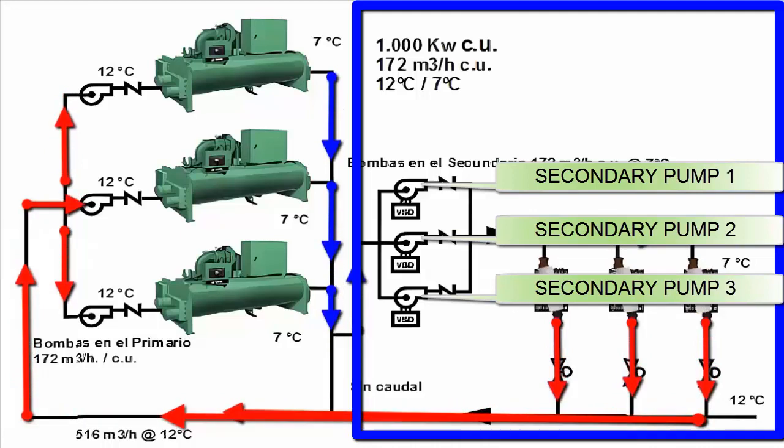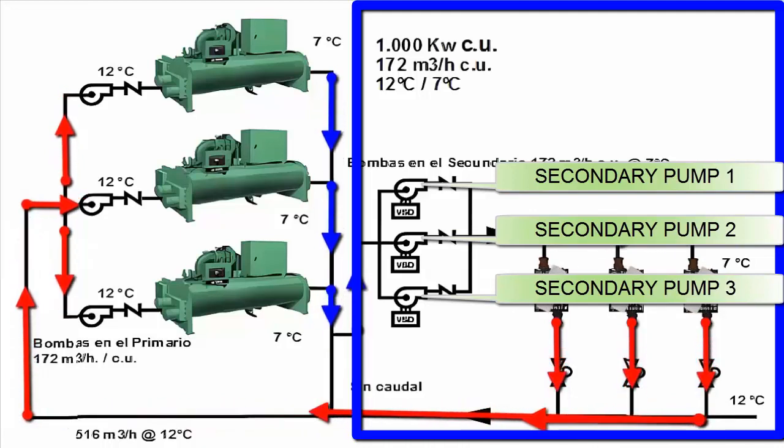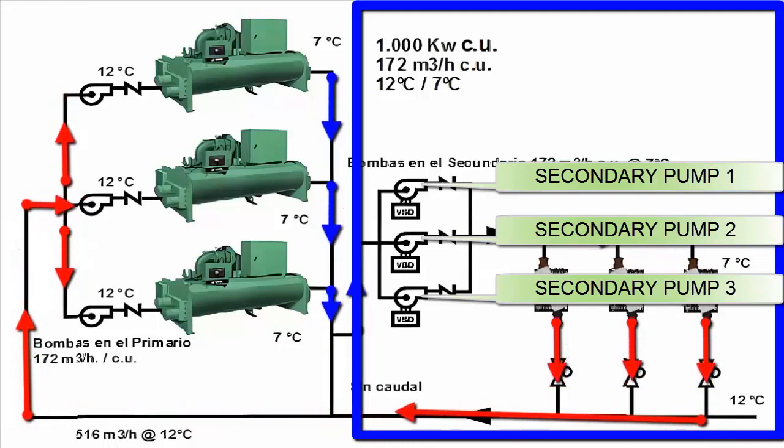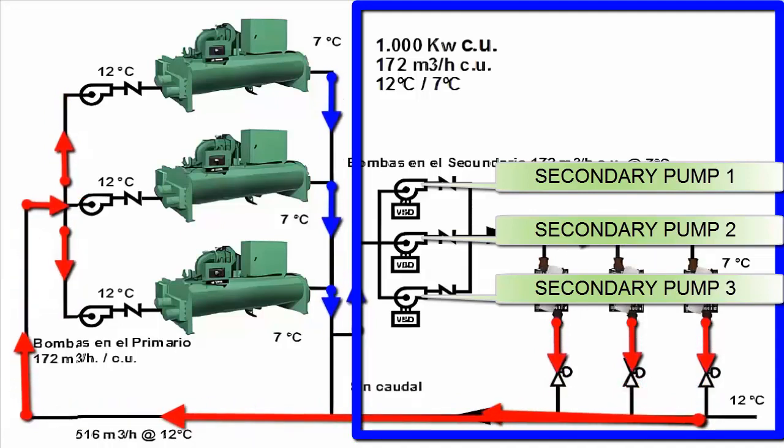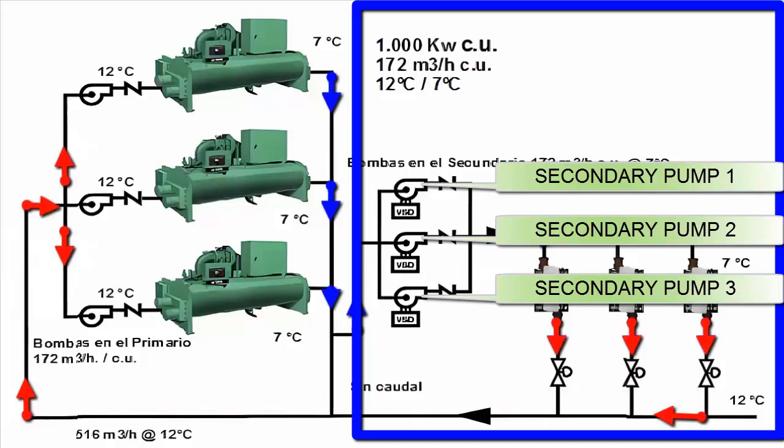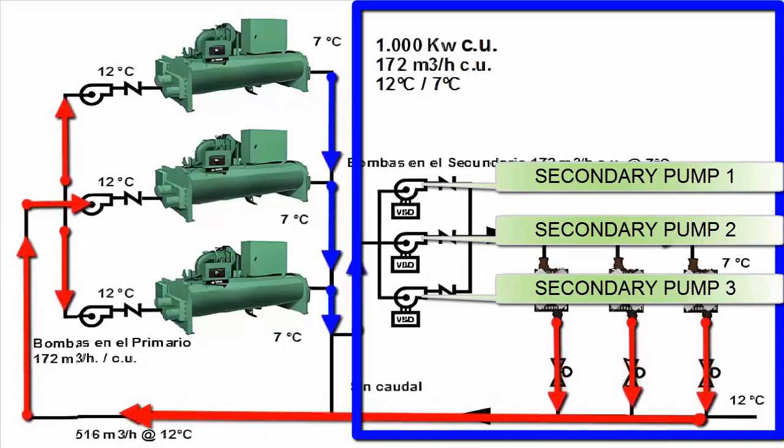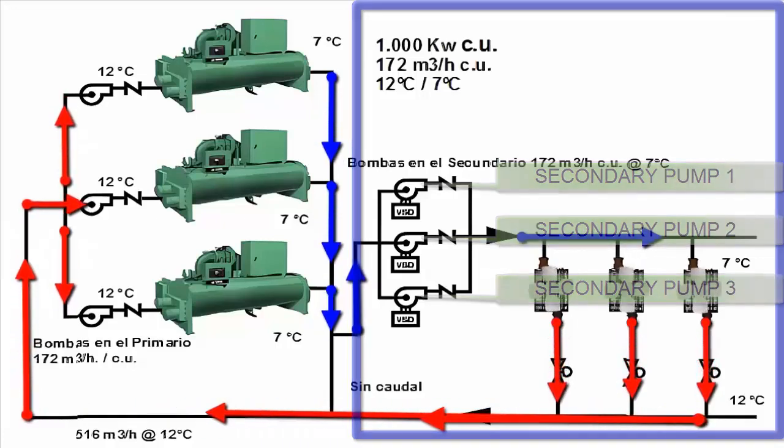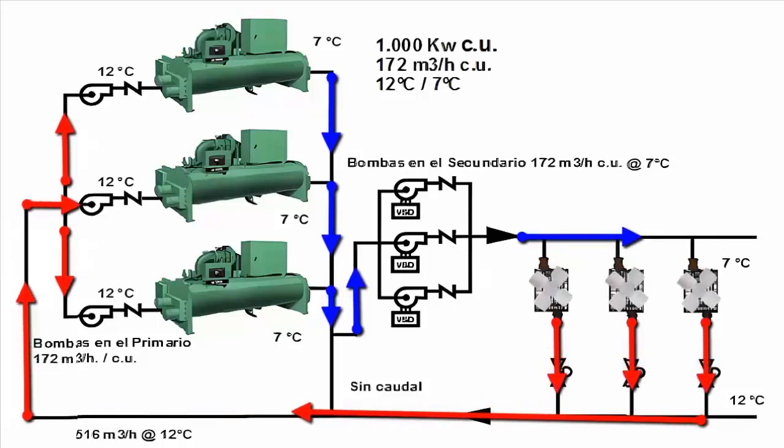This means the motors vary their speeds for RPM, which in turn changes the flow rate. The three pumps come together and send a single flow rate, while in the primary circuit, each pump sends water to its respective chiller.